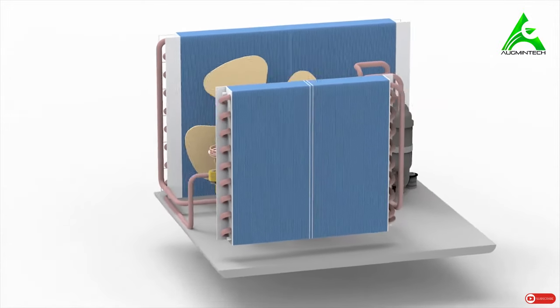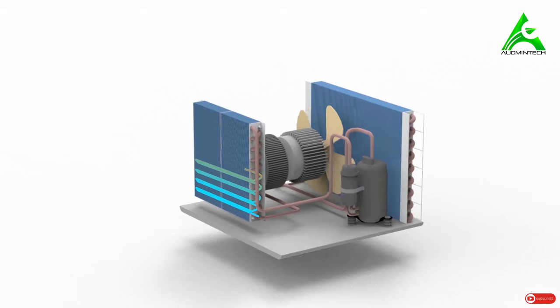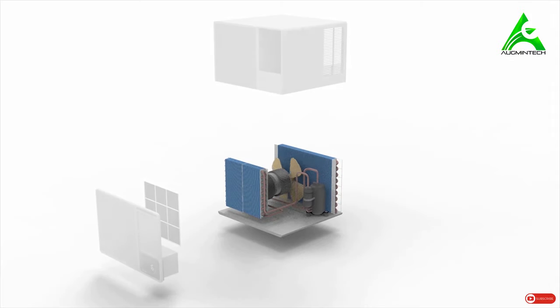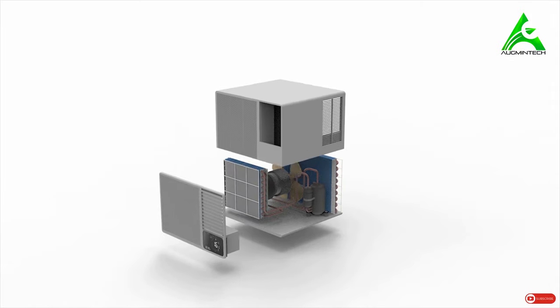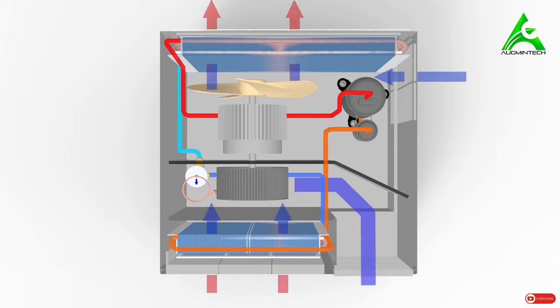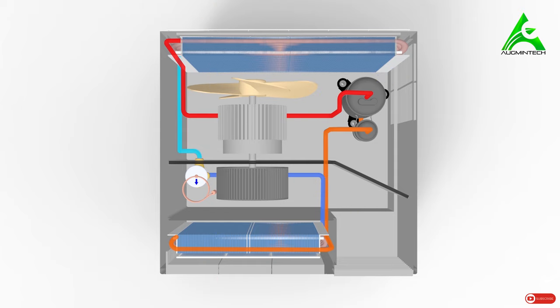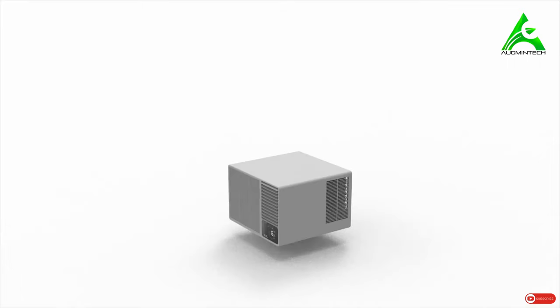This low temperature, low pressure liquid refrigerant again enters the evaporator and the cycle repeats itself. A motor installed inside the casing of the window air conditioner drives the fan near the condenser coil to achieve cooling of the refrigerant. The motor also drives the fan near the evaporator coil to blow air into the conditioned space. This is how cooling is achieved using a window air conditioner.